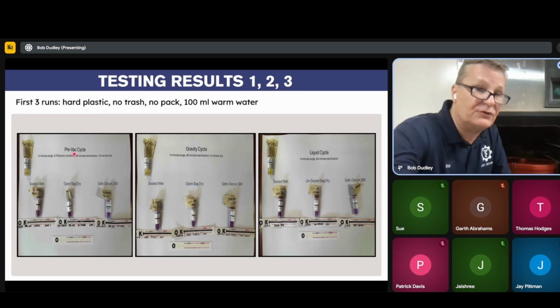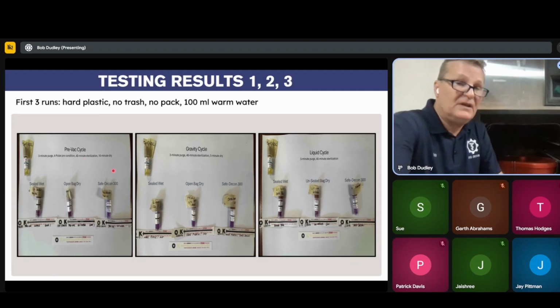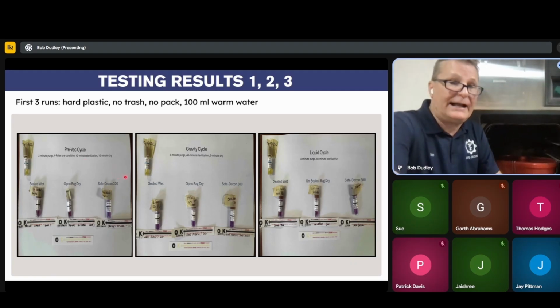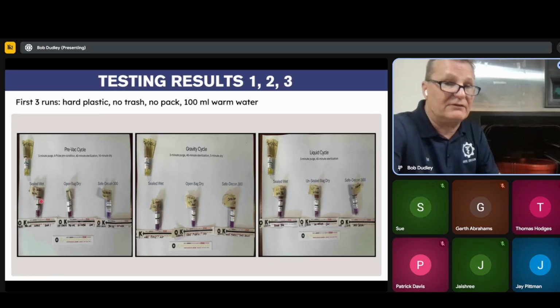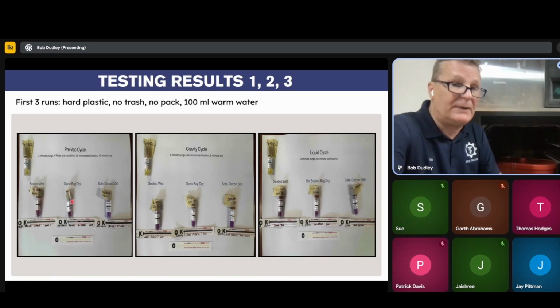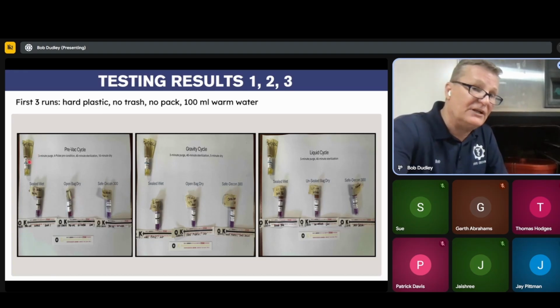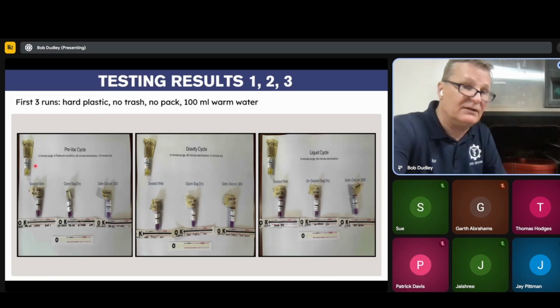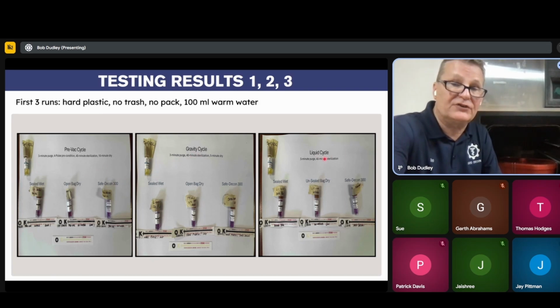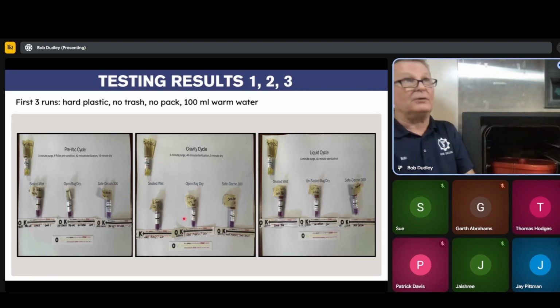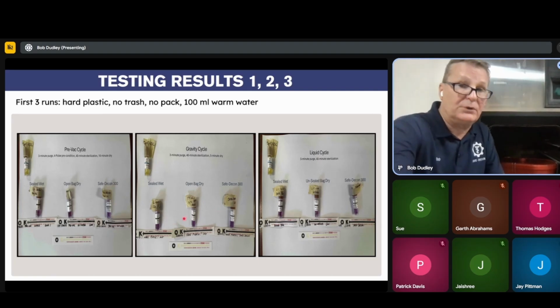Obviously, this was a pre-vac cycle, 3-minute purge, 4 pulse, preconditioning, 40-minute sterilization, with nothing blocking it, no trash. It truly was not that big of a deal. This bag, I did an open dry bag. I didn't even tape it. I just left it totally open. You can see my control here. This is the one I did not autoclave, obviously, just to make sure that my batch of biological indicators were still good. And away we go. So I ran a pre-vac, I ran a gravity, and a liquid cycle. I really didn't expect much trouble here because there really wasn't much to kind of block things.